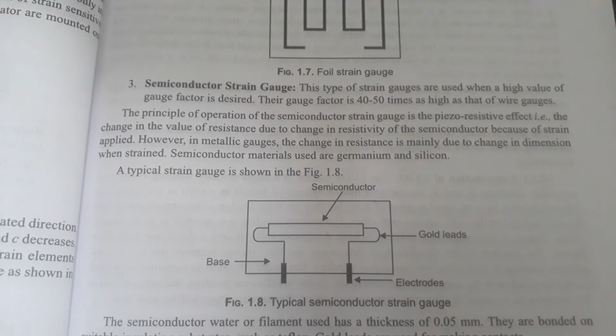The principle of operation of the semiconductor strain gauge is the piezoresistive effect. The change in the value of resistance is due to the change in resistivity of the semiconductor because of the strain applied. However, in a metallic gauge, the change in resistance is mainly due to the change in dimension. Germanium and silicon are used for the semiconductor strain gauge.